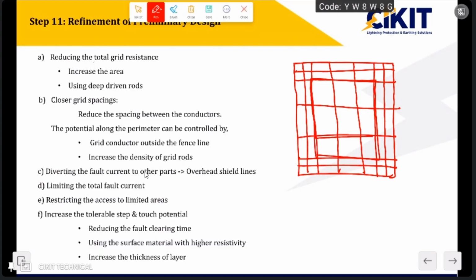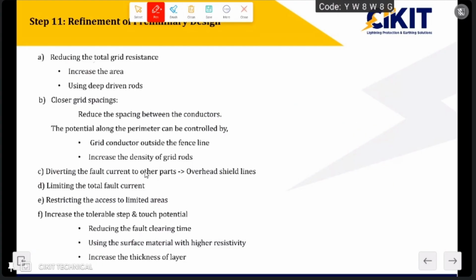And the next step is diverting the fault current to other parts. As I mentioned, if one substation has lots of feeder lines, then the ground wires or shield wires of these transmission lines will be connected to the network, and more fault current will be diverted through these ground wires or shield wires. So the portion of current entering the soil will be lesser. When we perform this calculation, we do it only for the current that travels through the soil to the source. Since the current is diverted to the ground wires or shield wires, the portion of current traveling through the soil will be reduced, and hence the value of Ig will be reduced.